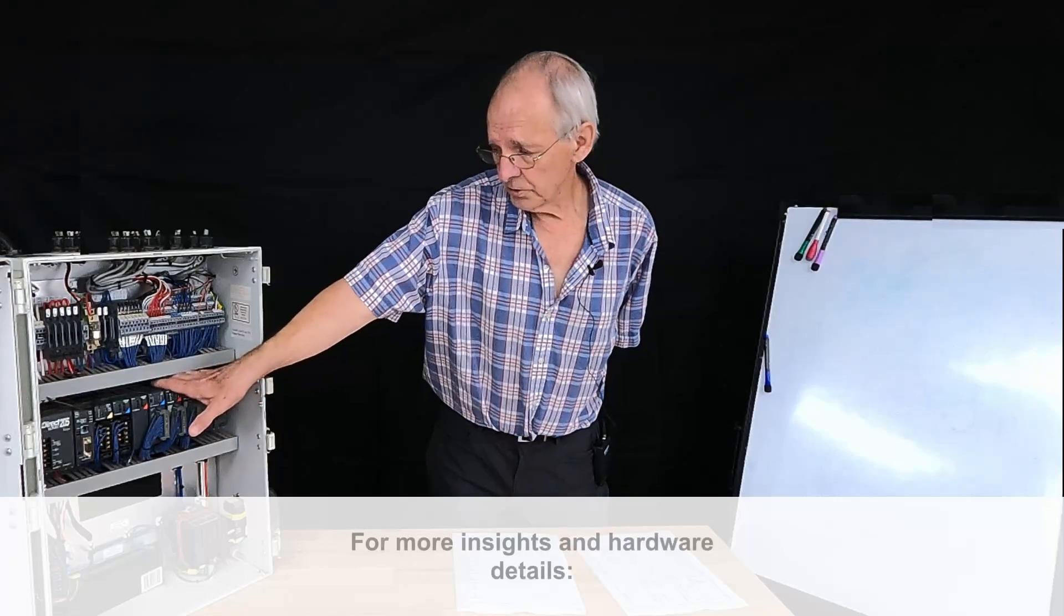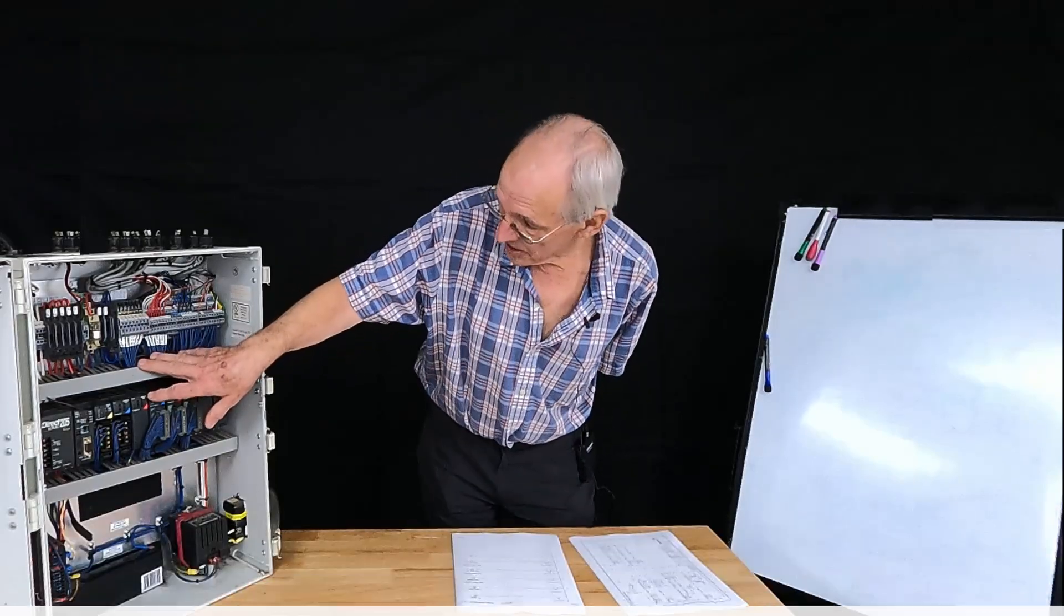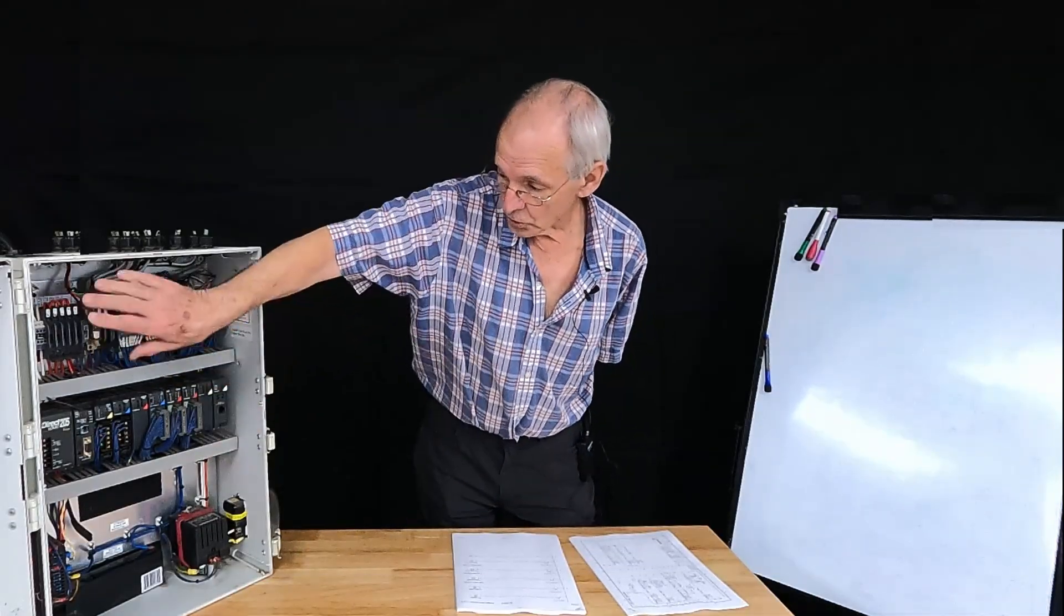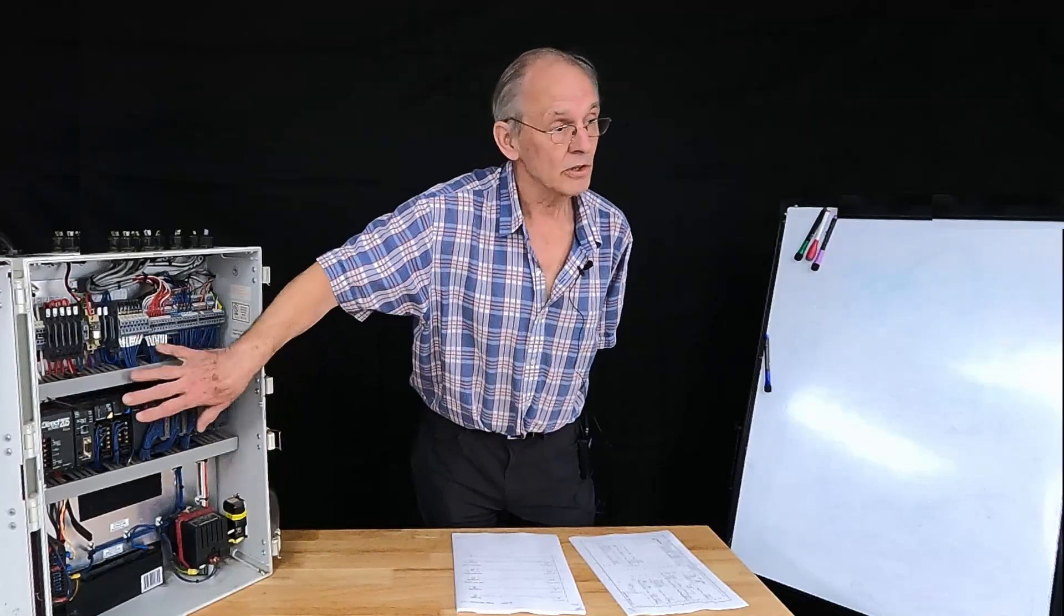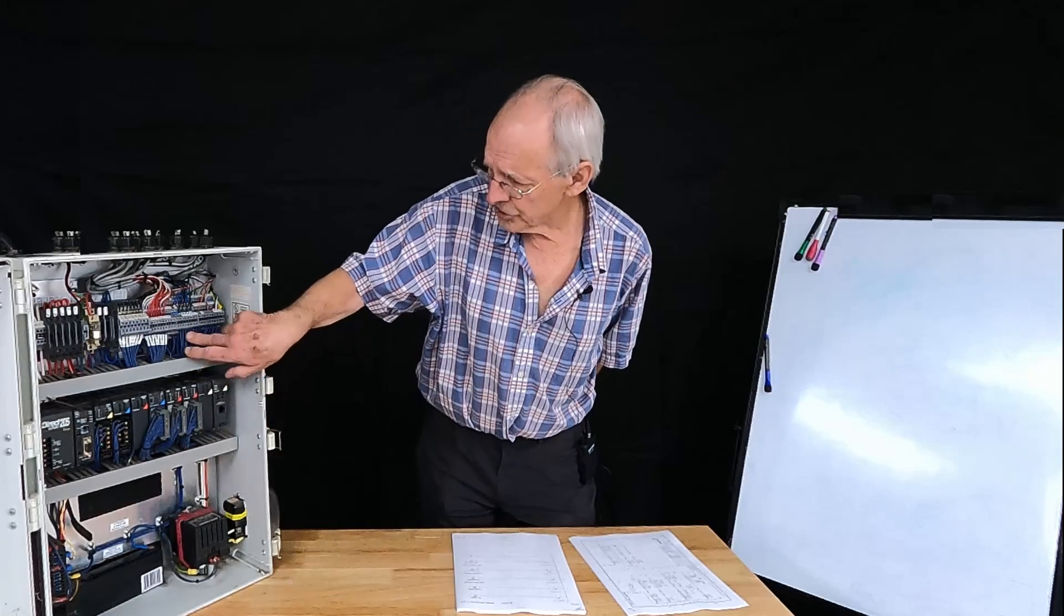If you notice here, in order for the wiring to get from one level to the other, it had to go under the PLC. And so there's no vertical wireways for wires, there's just the horizontal. And if you notice, there's no wire markers on a bunch of the wires.